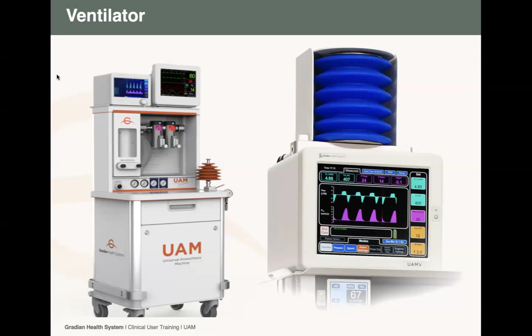Change from the top, then you come down, then you continue bagging the patient. Some of you, if you have done that, when you started the vent while the isolator switch is on the bag side, you will see the bag also coming up. And that's why the patient won't be ventilated. That's why we'll see the machine giving alarms. So always change the isolator switch to the vent side, and then you start the UAMV. Next.